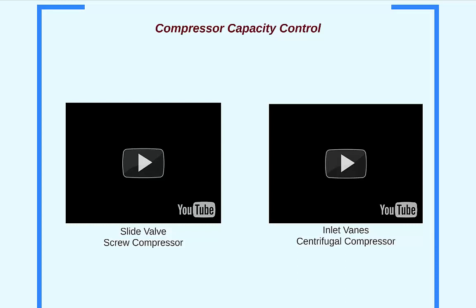Compressors may also be installed with internal capacity control to more accurately meet load. For screw compressors, slide valves are used to allow inlet gas to bypass portions of the compressor, which results in different levels of compression. This video shows the slide valve moving to 4 different locations, allowing the compression ratio to be adjusted between 25 to 100% of design.